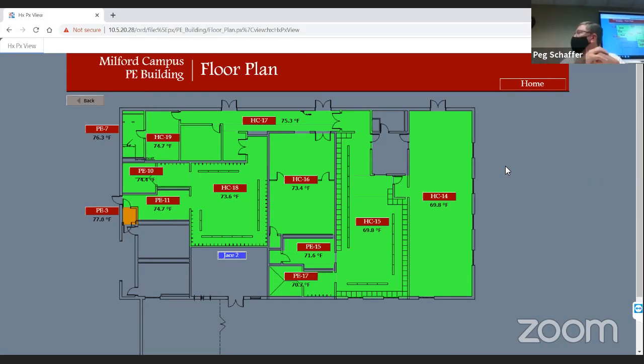He's speaking to a normal summer. This summer, we were occupied, with the dampers open to bring fresh air into the buildings every day, 24/7. So our energy costs are probably going to be a little higher, but because of COVID, that's what we felt we had to do. But the nice thing with the DDC system is you have the opportunity to make those changes in one location on the computer, and you can do that for all of your buildings. I'll show some simple demonstrations of that as I go through. But good point, Frank. Thank you.